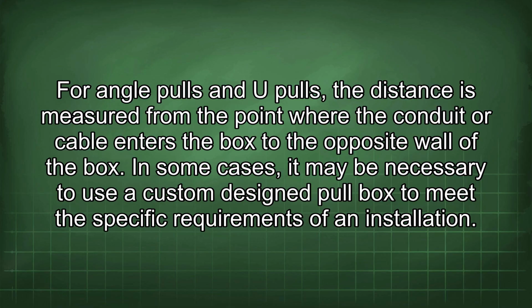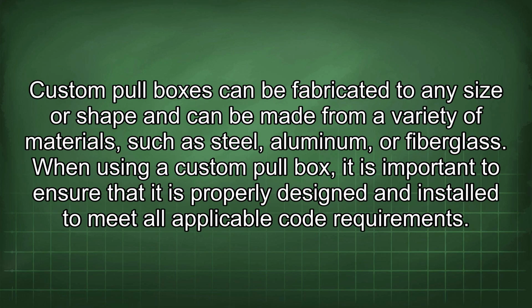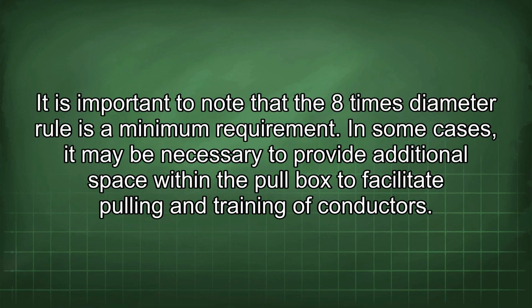In some cases, it may be necessary to use a custom-designed pull box to meet the specific requirements of an installation. Custom pull boxes can be fabricated to any size or shape and can be made from a variety of materials, such as steel, aluminum, or fiberglass. When using a custom pull box, it is important to ensure that it is properly designed and installed to meet all applicable code requirements. It is important to note that the 8 times diameter rule is a minimum requirement.